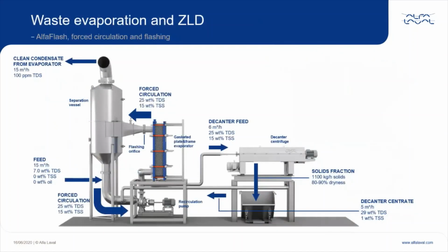To give an overview of the full ZLD evaporation system as designed and supplied by Alfa Laval, this picture shows the major components and flows for such a system. The feed, same properties as previously shown for the generic case, is mixed with a large flow of fluid from the separator vessel. The recirculation pump, installed at the bottom, sends this mixture through the gasketed plate and frame evaporator using the corrugated plates in titanium material for forced circulation and flashing evaporation. The plate corrugation gives the high turbulence and shear forces, helping to reduce fouling and scaling, and the titanium material will help to prevent corrosion.